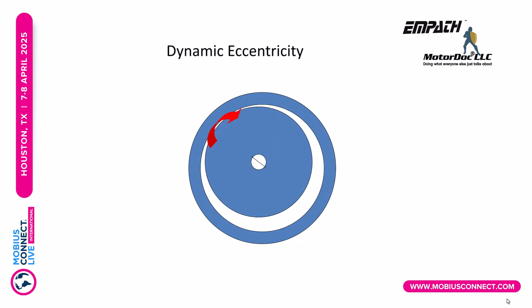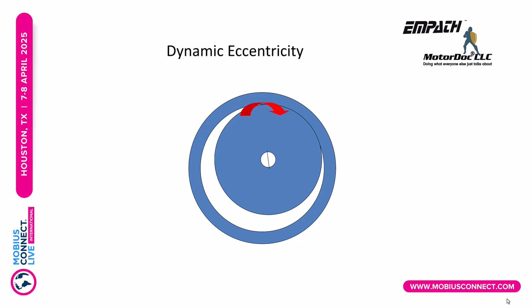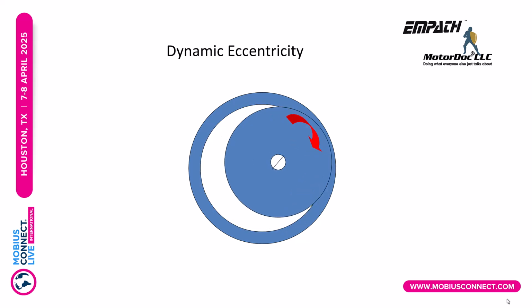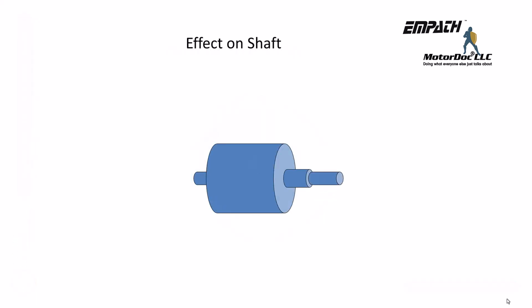And if it's orbiting inside the air gap, whether that's a mechanical orbit or a magnetic orbit. A magnetic orbit means the rotor's sitting dead center, but there's an unbalance in the fields in the rotor that cause it to appear to orbit. That's called dynamic eccentricity. You can have one, the other, or both. The other things you can have is an unbalance. You can have torsional issues.